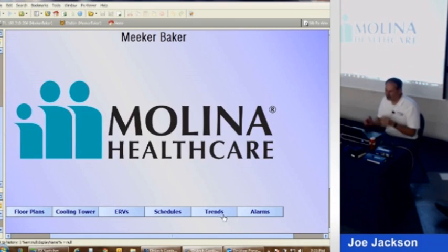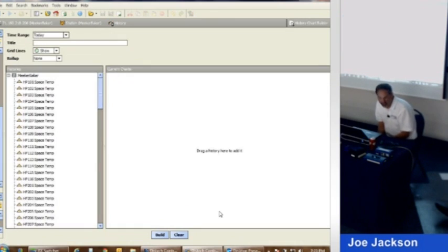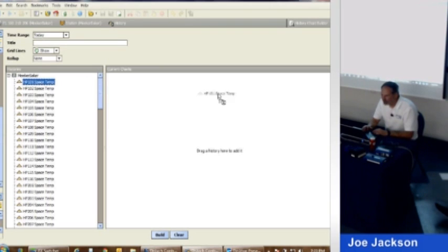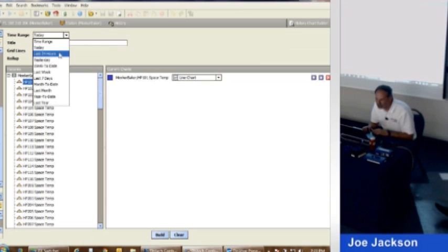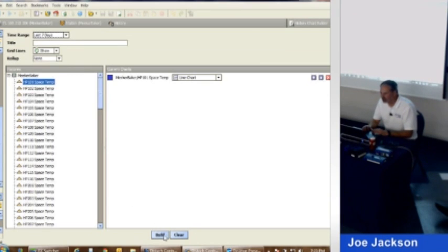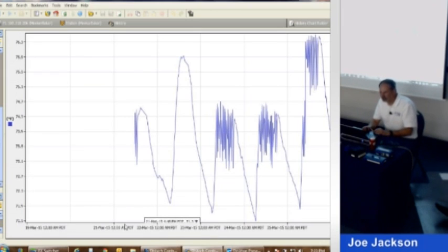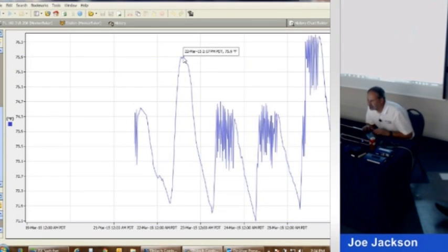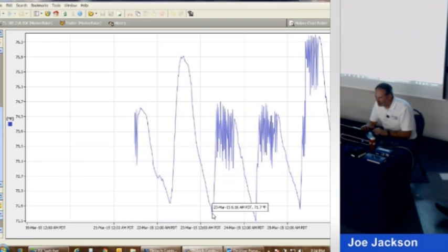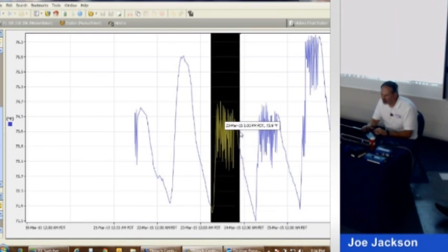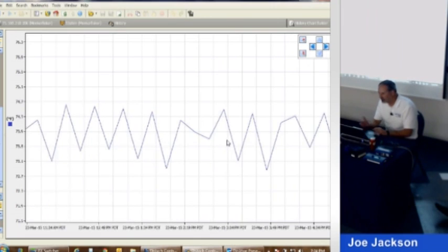It also does trends. It can remember anything you ask it to remember. You do have to ask it. I'll just take the space temperature of this heat pump. We'll drag him over there, and I want to see it for the last 7 days. And I tell it to build me a chart. And there it is. Looks like it went crazy, but it's not as crazy as it looks. It only went as high as 75 degrees, and it did that at 2 p.m. Went to 75.9 degrees, and it's gone as low as 71 degrees. And if we want to zoom in and see what's going on right here, we just take this, zoom in, there it is. Or if you want to see that section, you can keep zooming in as much as you want. So anything you ask it to remember, it will, and you can retrieve that depending on how long you ask it to save it.